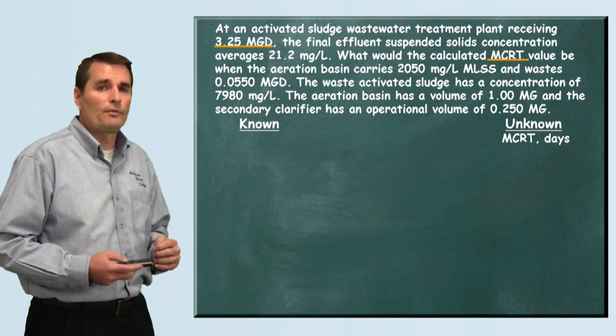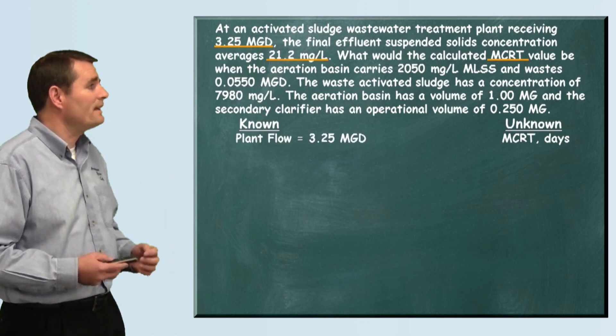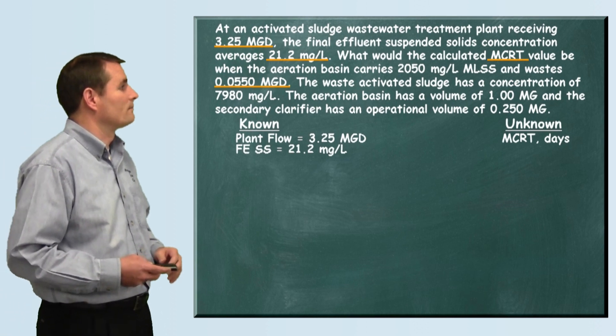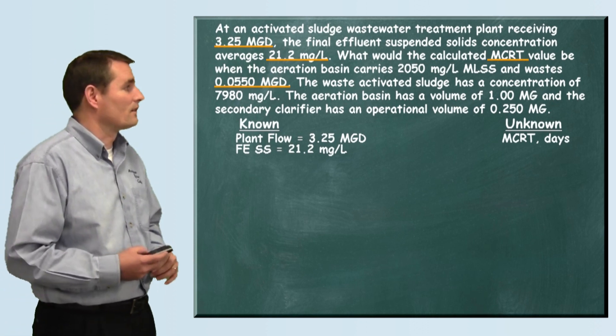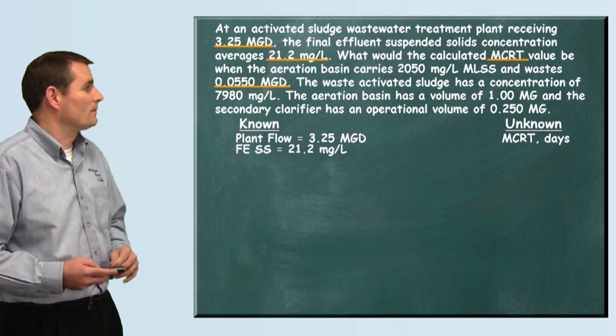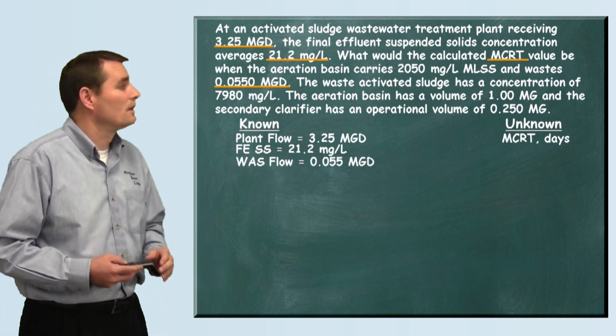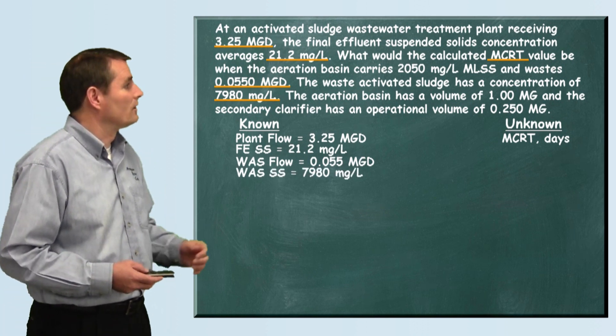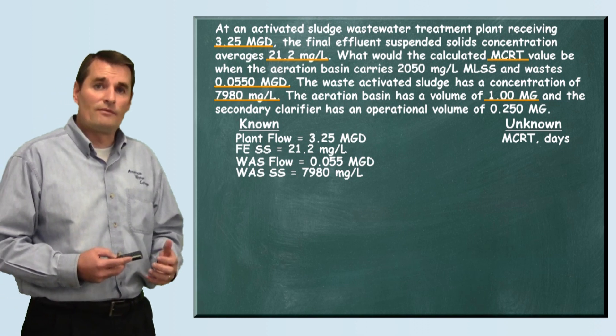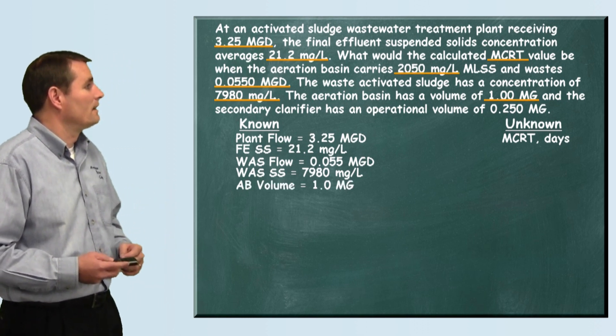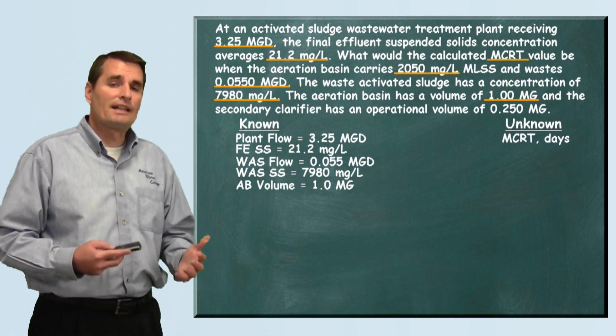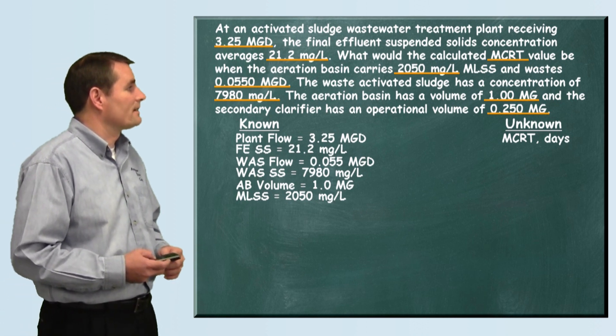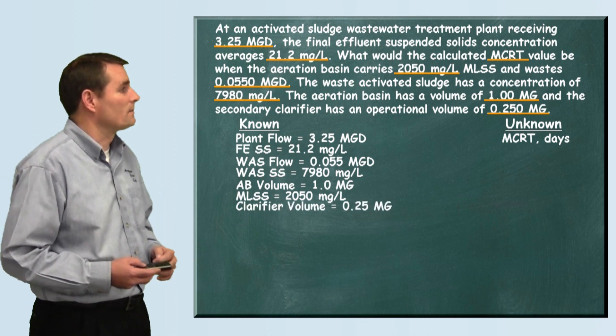Plant flow is 3.25 million gallons per day. The concentration of solids leaving the plant is 21.2 milligrams per liter. We're wasting sludge at a rate of 0.0550 million gallons per day — that's our WAS flow. The concentration of our waste activated sludge is 7,980 milligrams per liter. The aeration basin volume is 1 million gallons, carrying mixed liquor suspended solids at 2,050 milligrams per liter. The secondary clarifier has an operational volume of 0.250 million gallons.